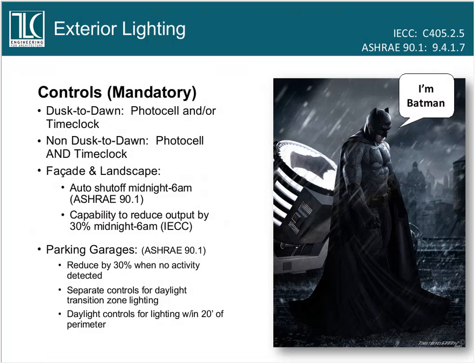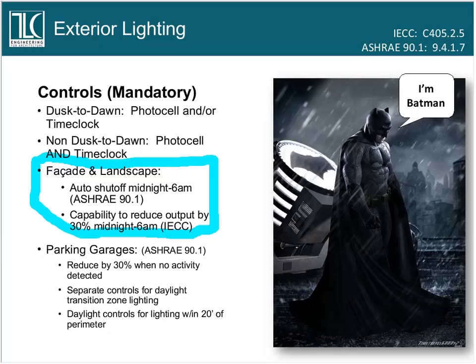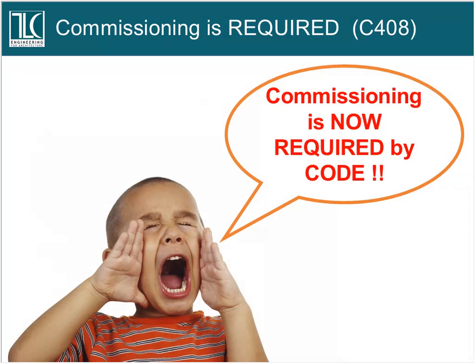Exterior lighting now works very similar to the way that we do it in LEED, where it's sensitive to whether you're in an urban zone or a rural zone. There's now a requirement that facade and landscape lighting be shut off from midnight to 6 a.m. It used to be that those lights ran all night long. Now they have to shut down or reduce output in the midnight to 6 a.m. hours. Once again, mandatory. You don't have a way to get out of this by running an energy model.